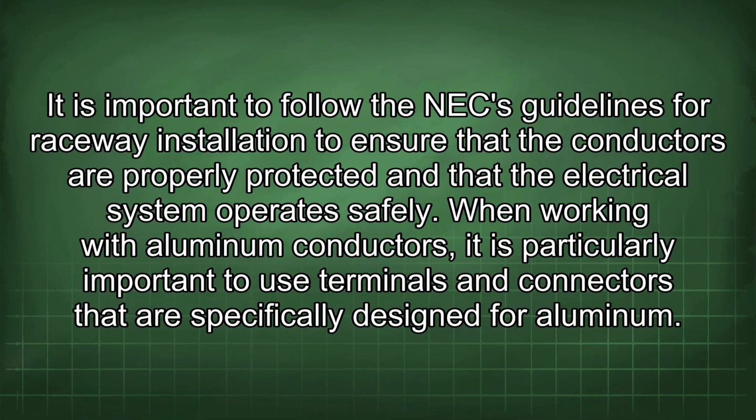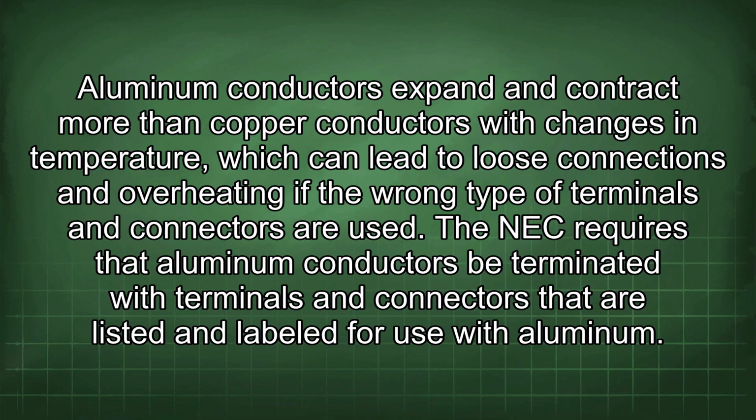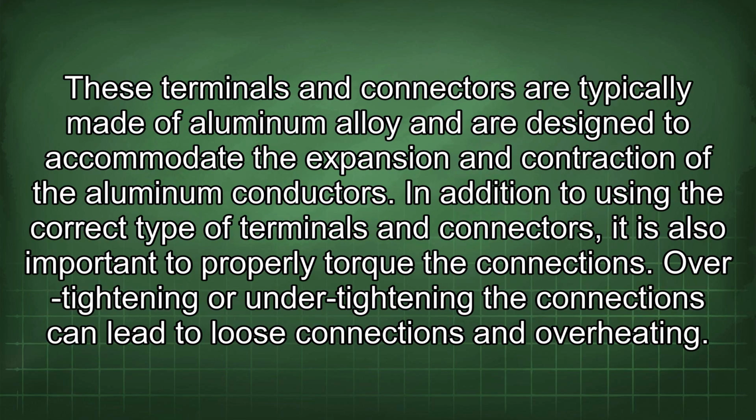When working with aluminum conductors, it is particularly important to use terminals and connectors that are specifically designed for aluminum. Aluminum conductors expand and contract more than copper conductors with changes in temperature, which can lead to loose connections and overheating if the wrong type of terminals and connectors are used. The NEC requires that aluminum conductors be terminated with terminals and connectors that are listed and labeled for use with aluminum.